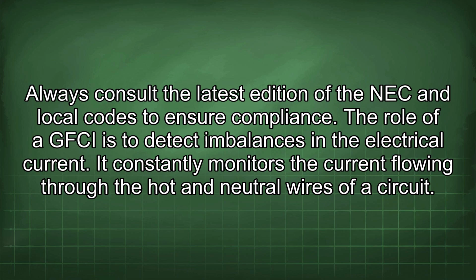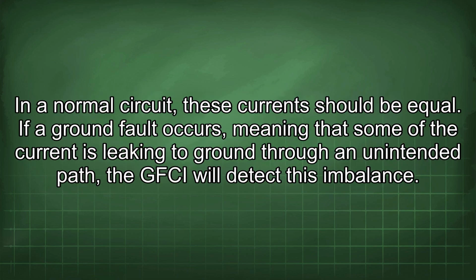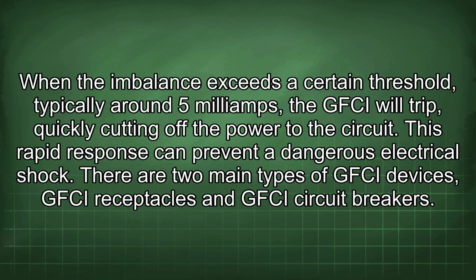The role of a GFCI is to detect imbalances in the electrical current. It constantly monitors the current flowing through the hot and neutral wires of a circuit. In a normal circuit, these currents should be equal. If a ground fault occurs, meaning that some of the current is leaking to ground through an unintended path, the GFCI will detect this imbalance. When the imbalance exceeds a certain threshold, typically around 5 mA, the GFCI will trip, quickly cutting off the power to the circuit. This rapid response can prevent a dangerous electrical shock.